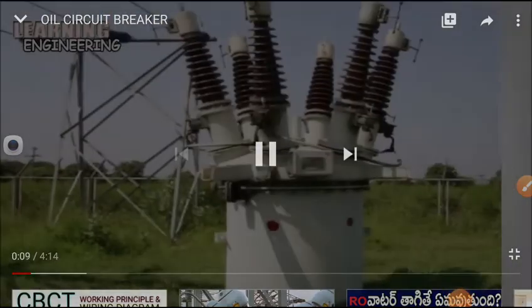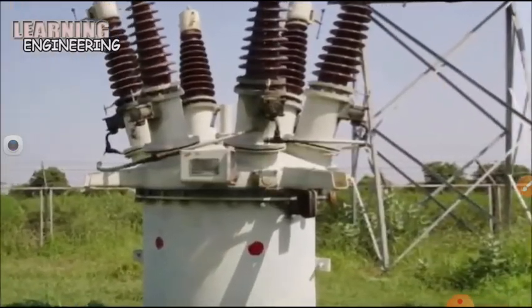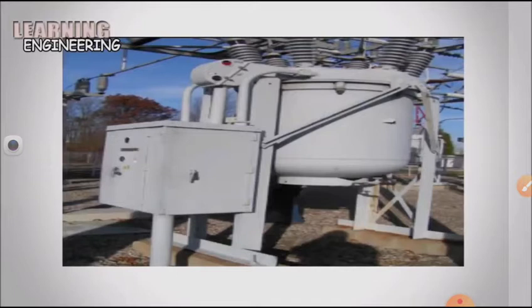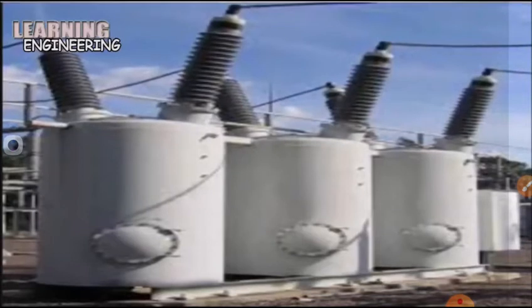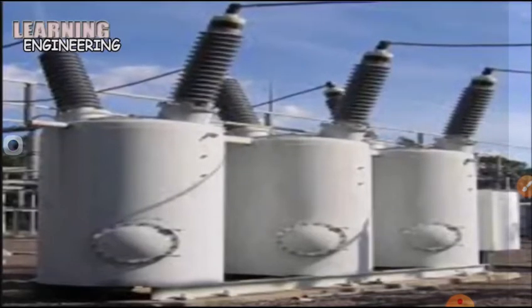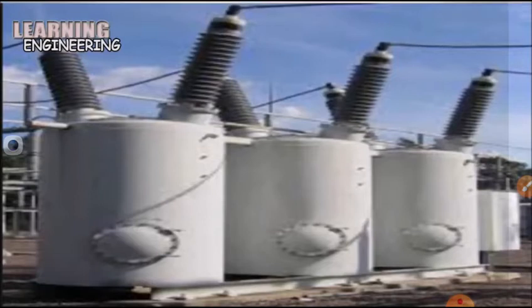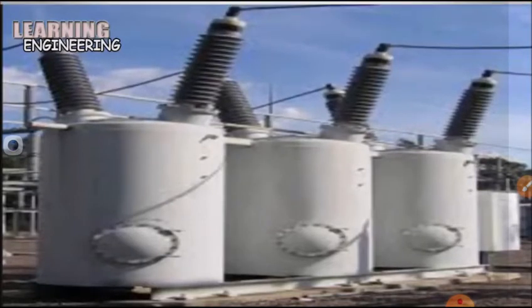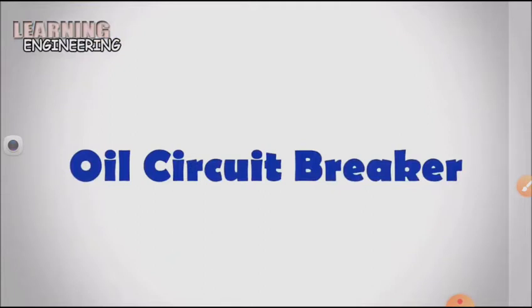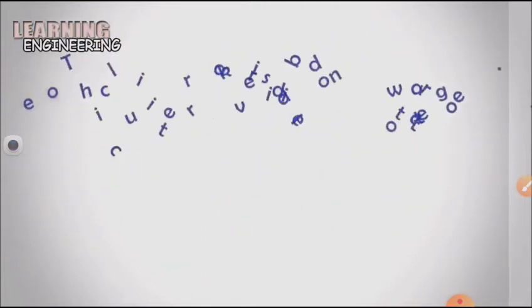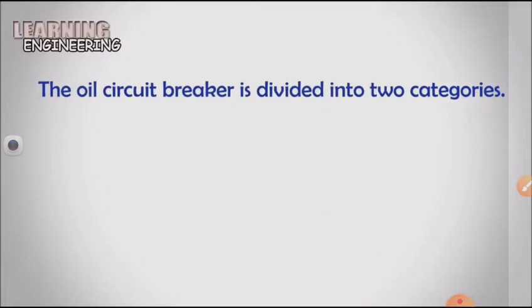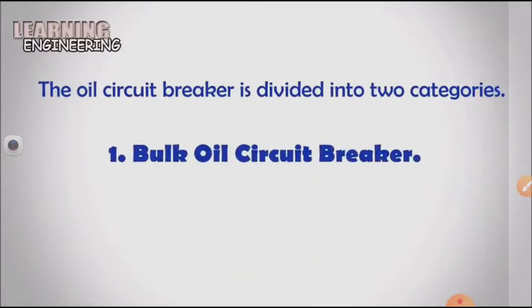One more explanation of the oil circuit breaker. An oil circuit breaker is a type of circuit breaker which uses oil as a dielectric or insulating medium for arc extinction. In the oil circuit breaker, the contacts of the breaker are made to separate within an insulating oil. When a fault occurs in the system, the contacts of the circuit breaker separate, and an arc is developed between them, and the heat of the arc evaporates the surrounding oil. The oil circuit breaker is divided into two categories: 1. Bulk oil circuit breaker. 2. Low oil circuit breaker.